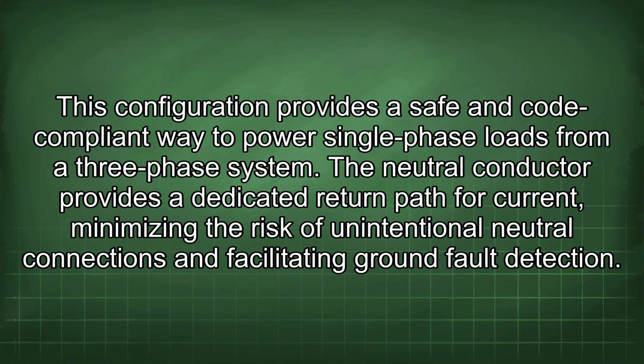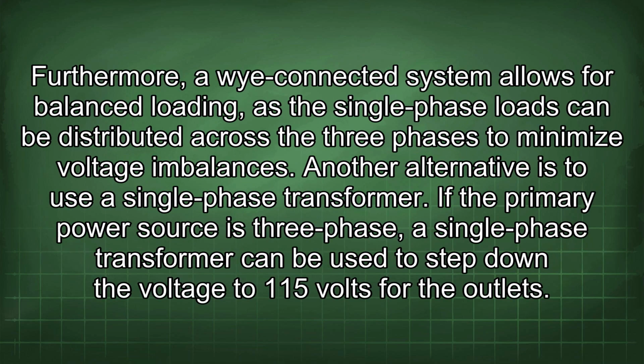The neutral conductor provides a dedicated return path for current, minimizing the risk of unintentional neutral connections and facilitating ground fault detection. Furthermore, a Y-connected system allows for balanced loading, as the single-phase loads can be distributed across the three phases to minimize voltage imbalances.